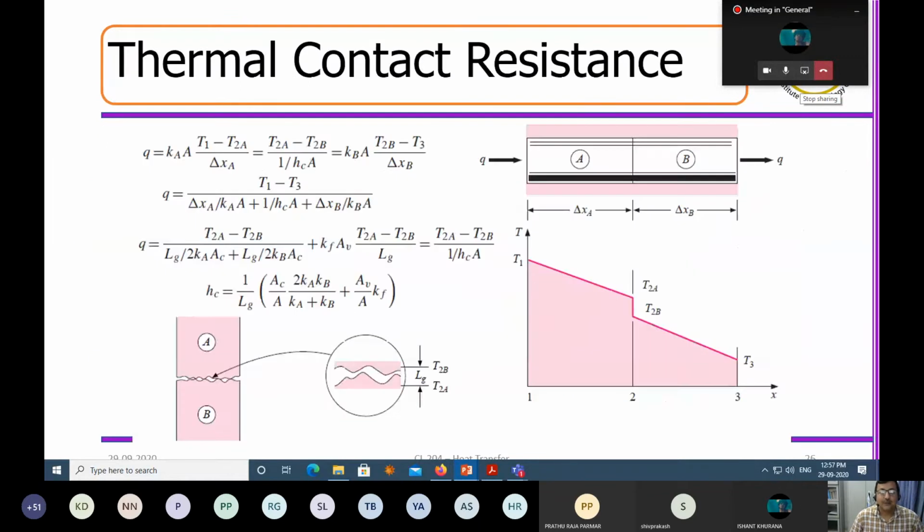Right. Now, once that has happened, one thing you should always worry about is that whenever you do insulation, there will be a gap. Okay, there can be air gaps, there can be non-conformal contacts, which will create insulation layers like this. You have to be absolutely careful because whenever you are designing, you have to keep some parameters associated with this, which should come into the engineering design, which will take care of these losses. Suppose you have an air gap between two insulators, that will add to your resistance. Okay. Now most of the calculations go bad because people do not consider this part.